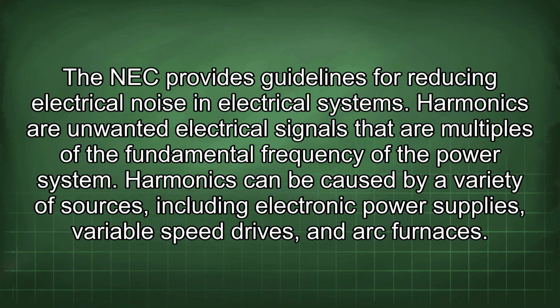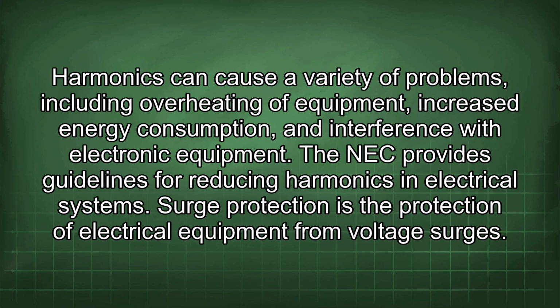Harmonics are unwanted electrical signals that are multiples of the fundamental frequency of the power system. Harmonics can be caused by a variety of sources, including electronic power supplies, variable speed drives, and arc furnaces. Harmonics can cause a variety of problems, including overheating of equipment, increased energy consumption, and interference with electronic equipment. The NEC provides guidelines for reducing harmonics in electrical systems.